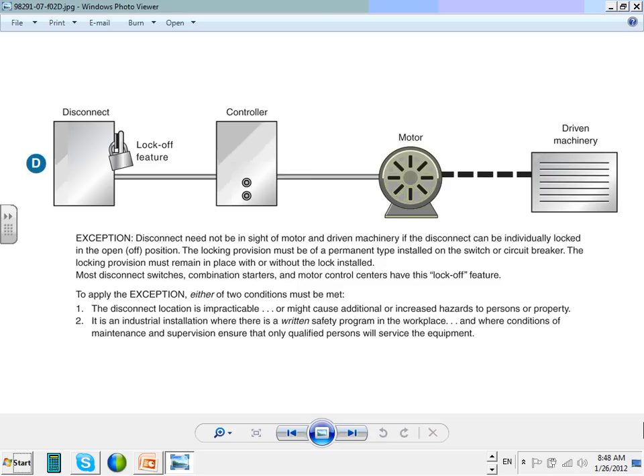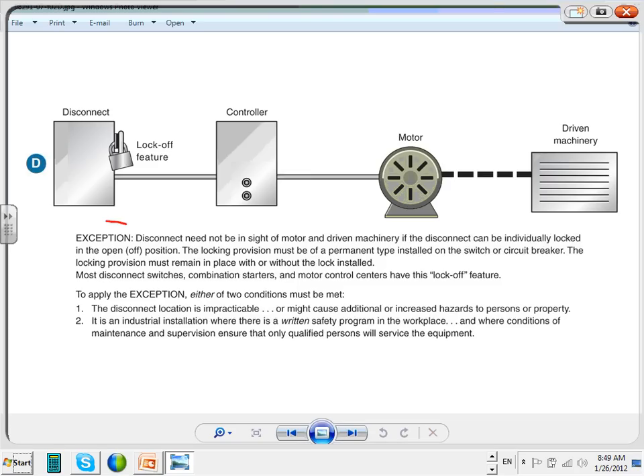And again, I can't emphasize, it is an exception where you can have your disconnect located anywhere else in the building, and you have your controller, motor and machine located anywhere else from each other or from the disconnect. But you have to be careful. Then your disconnect has to be able to be locked in the open position, like you can see. All of them can be locked, as you can see on the wall here. And here's how to apply the exception. The disconnect is, I can't emphasize, here's the word: it's impractical to put the disconnect next to the equipment.